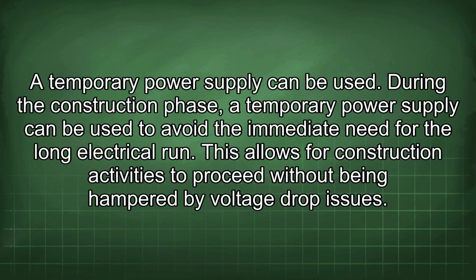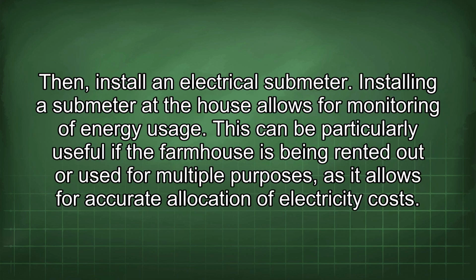A temporary power supply can be used. During the construction phase, a temporary power supply can be used to avoid the immediate need for the long electrical run. This allows for construction activities to proceed without being hampered by voltage drop issues. Then install an electrical submeter. Installing a submeter at the house allows for monitoring of energy usage. This can be particularly useful if the farmhouse is being rented out or used for multiple purposes, as it allows for accurate allocation of electricity costs.